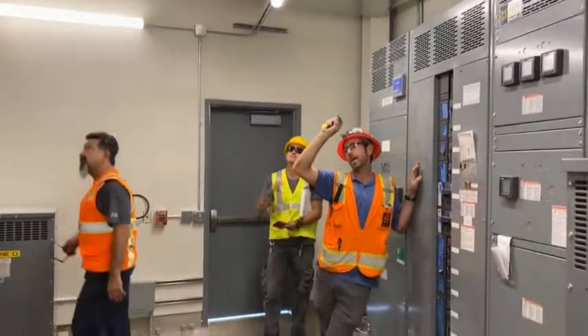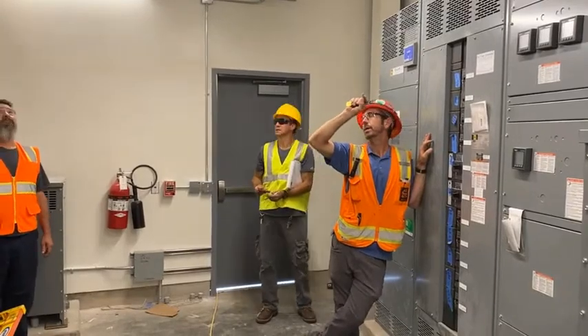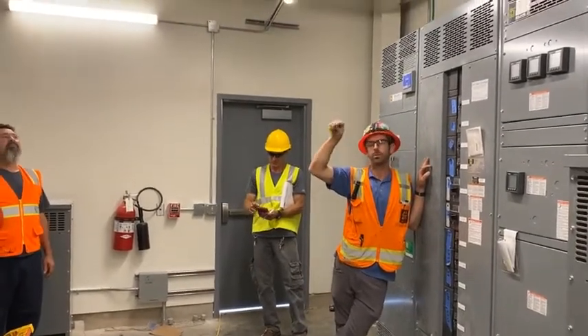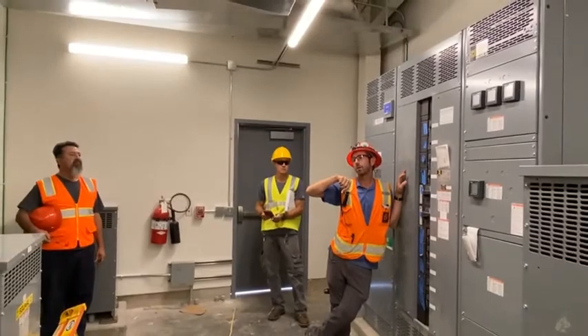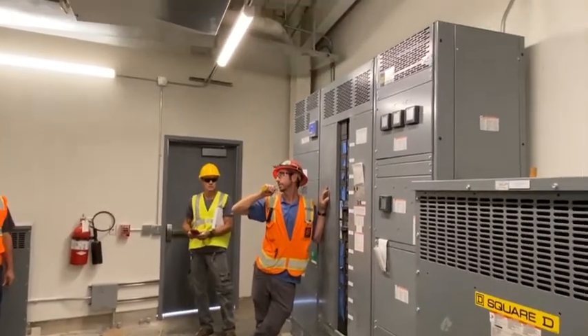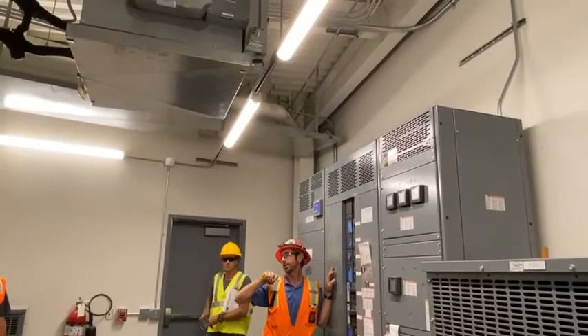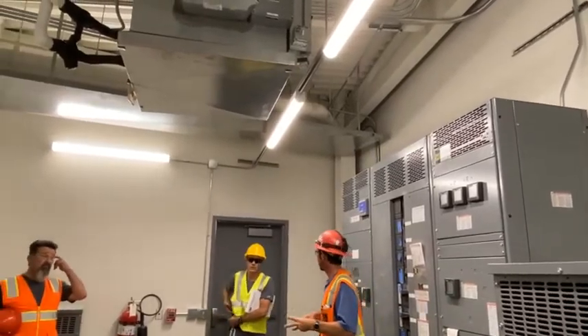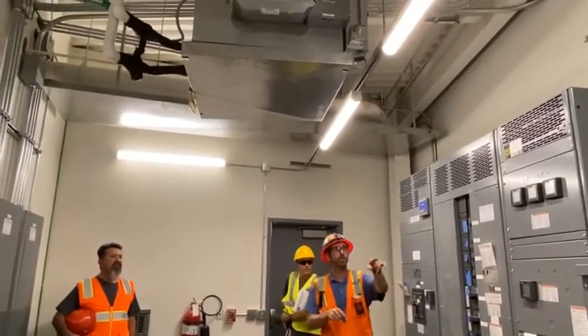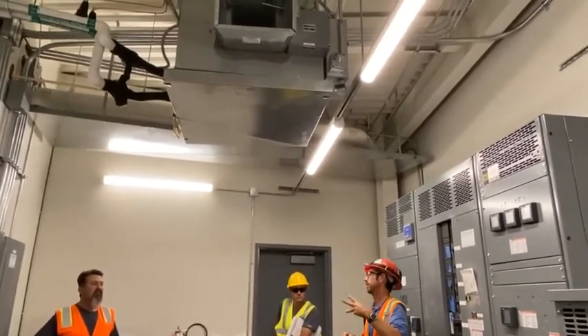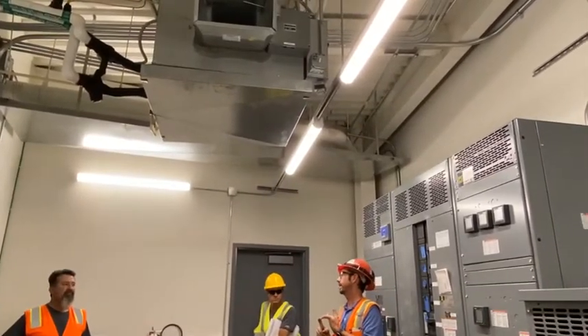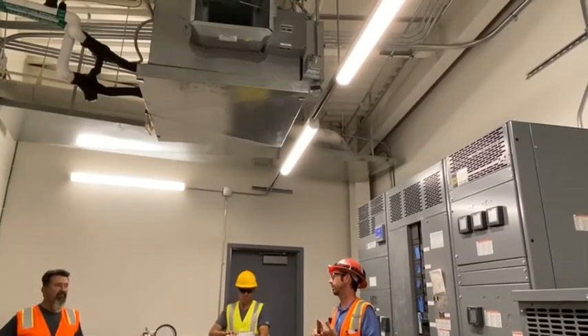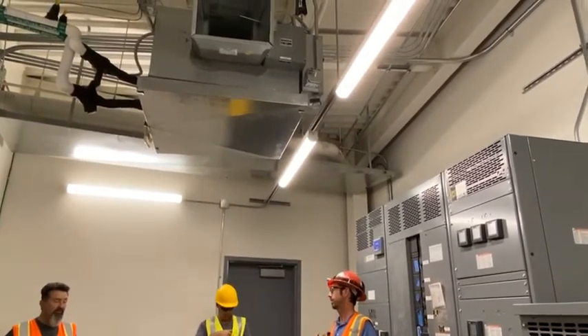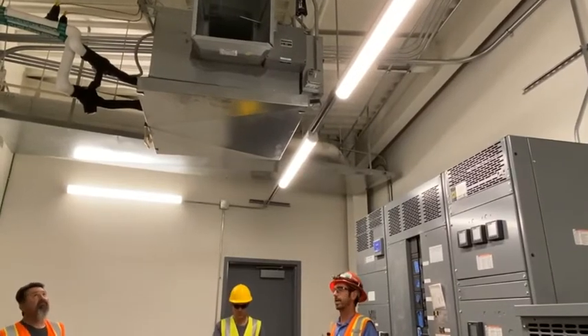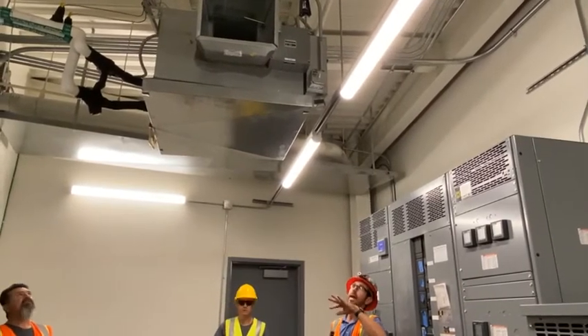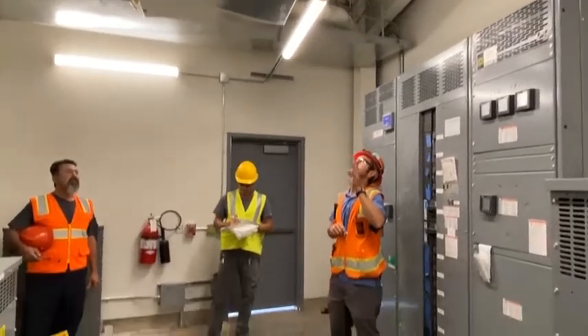So these are direct drive ECM motors. Okay. The fan coils over here for you guys are all 0 to 10 volt speed signal control. But the control guys are just taking 3 speeds. So we didn't have to worry about the rooms. There's 3 speeds. So like this one, 3 volts is high speed, 2 volts is medium speed, and 1 volt is low speed. So highest voltage is the highest speed. That gives us the design CFM that the engineer wants.